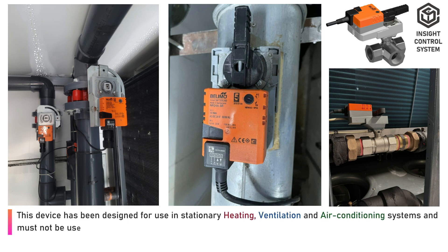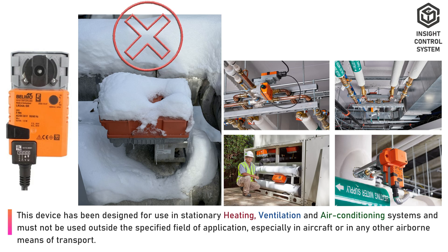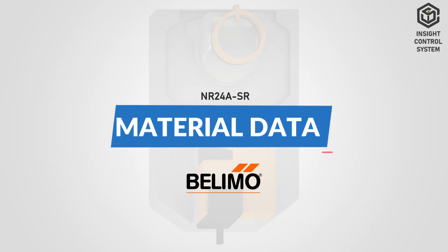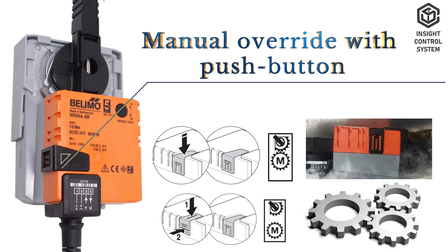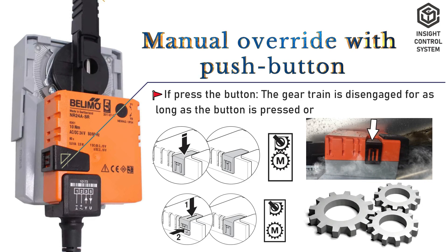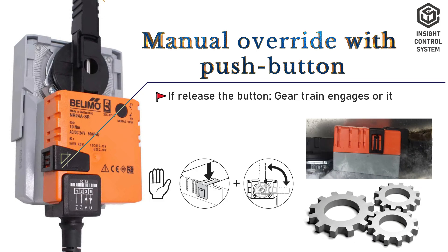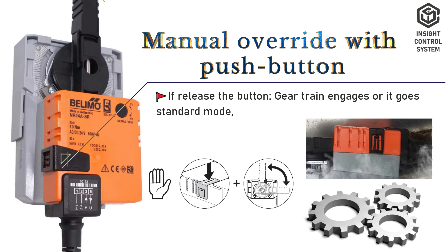This device has been designed for use in stationary heating, ventilation, and air conditioning systems, and must not be used outside the specified field of application. This is the manual override with push button. If you press the button, the gear train is disengaged for as long as the button is pressed or remains locked. If you release the button, the gear train engages and it goes back to standard mode.